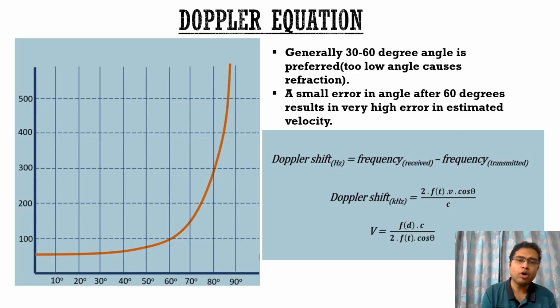So coming to the very important question, at what angle should we keep the probe to get the best results? It's generally 30 to 60 degrees. Very low angles cause refraction, and after 60 degrees, even a small error in the angle causes a very large error in the estimated velocity. As you can see in this graph, after 60 degrees, see the slope of this graph. These are the velocities. So after 60 degrees, even a small change can lead to a large error in the estimated velocity.